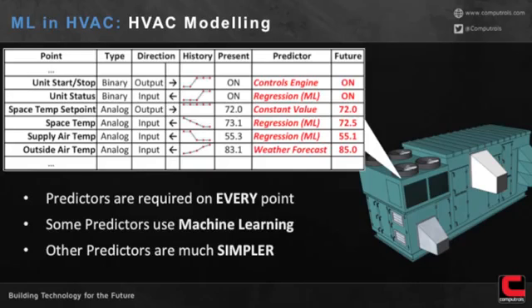And we have history on all these points—a year of data on every one of these things. So not only do we have the present value, but we have predictors on every one of them. You'll see controls engine, that's the actual building automation system, that's what we use to predict the output. Regression, which I'll go over in a minute, is the sort of go-to type of algorithm for machine learning—that's used on three different ones. And at the bottom, outside air temperature, we're going to predict that just using a good old-fashioned weather forecast.